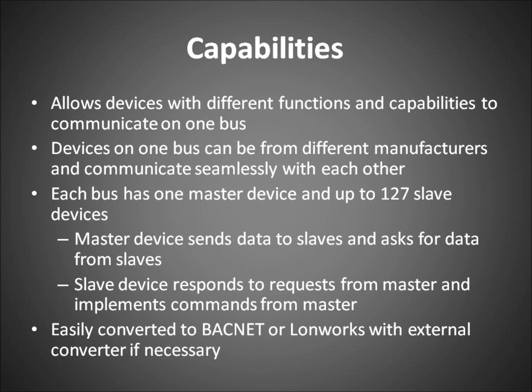The capabilities. As we know in the heating business, especially in commercial, a lot of people want to be able to read information of what their systems are doing and actually interact with the equipment. So the capabilities of this ModBus will allow devices with different functions and capabilities to communicate on one bus. Devices on one bus can be from different manufacturers and can communicate seamlessly with each other. Each bus has one master device and up to 127 slave devices. Master devices send data to the slaves and ask for data from the slaves. Slave devices respond to requests from the master and implement commands from the master. Easily converted to BACnet or LonWorks with external converters if necessary.